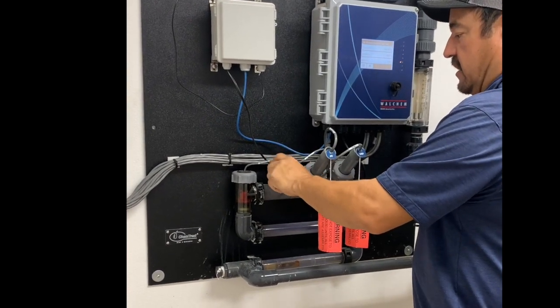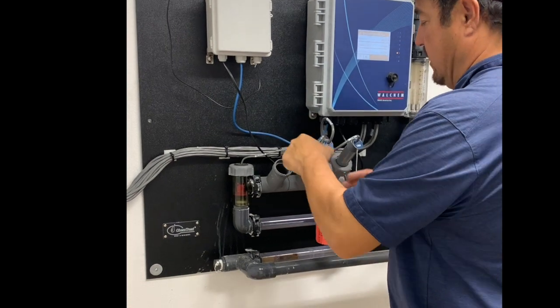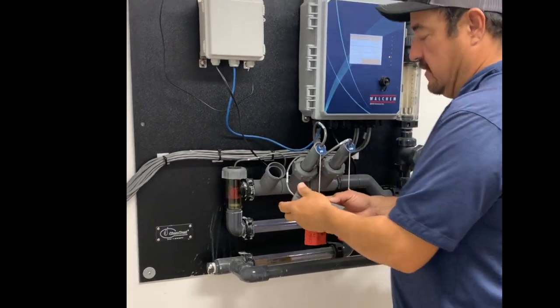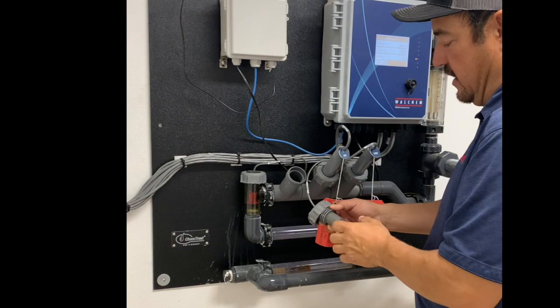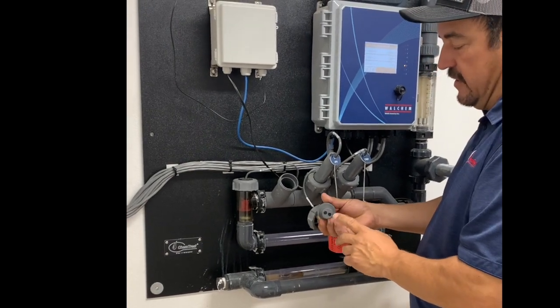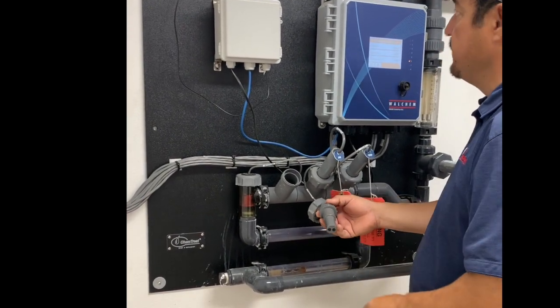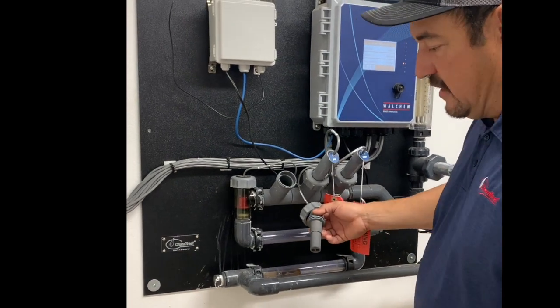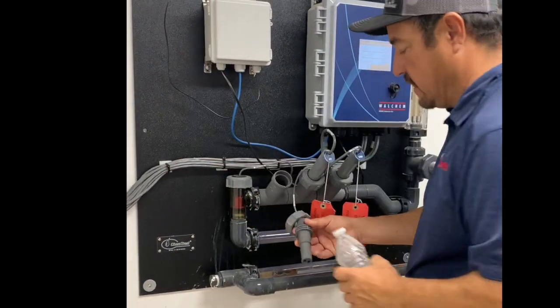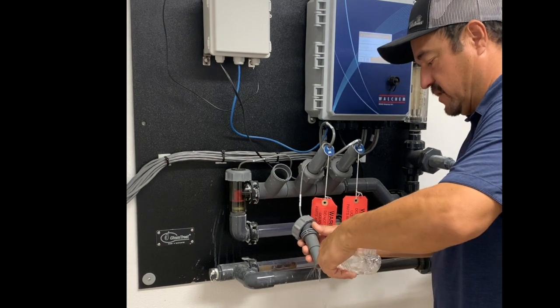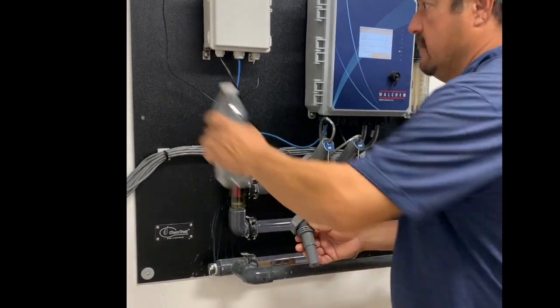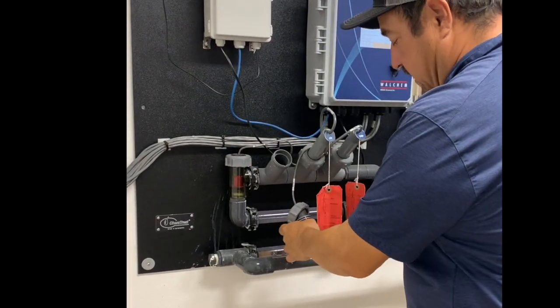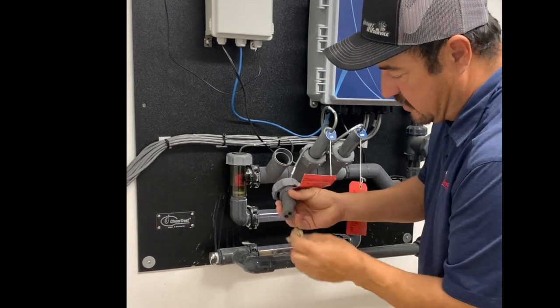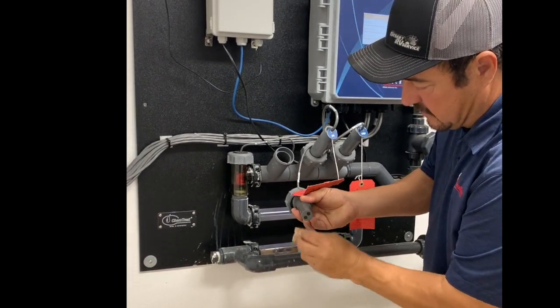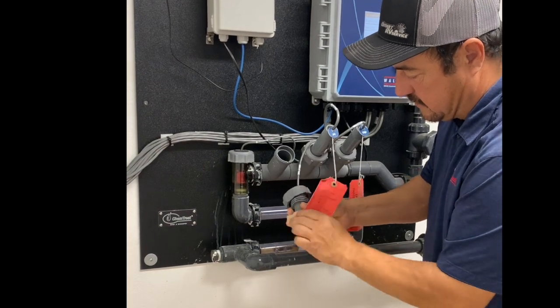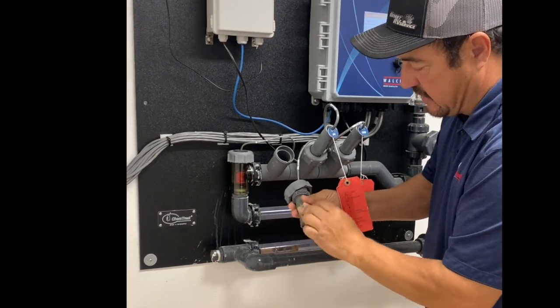In this case, we're going to do the conductivity, but we're going to show you also a probe on the pH so you can see it. So this probe here, we're going to make sure that this part is clean here. And there's a couple ways you can do it depending on how dirty it is, but kind of just rinse it off with a light cloth. You can just clean the probe. Make sure it's not dirty, clean around it. And you can put that back into service.